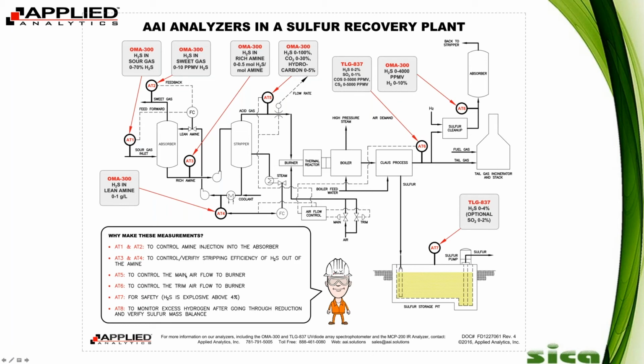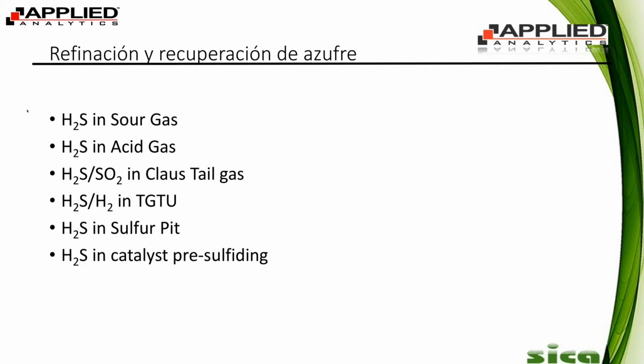There's also the acid gas measurement, which is very similar. It's usually higher percent H2S. We can go 0 to 100% H2S, with a plus or minus 2% full scale accuracy. So those are very similar measurements for the analyzer itself. Both very easy, pretty standard for SRUs around the world. 5% H2S applications are great for our equipment.